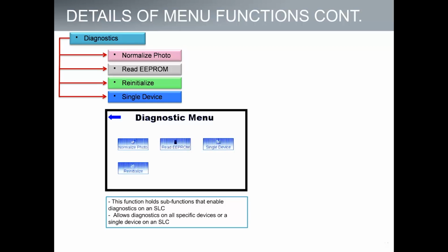Next, single device function. The single device function allows a user to diagnose a single device within a loop or outside a loop. The single device function consists of 5 sub-functions, which include read EE data, photo AD value, program device address, program maintenance date, and trouble codes.